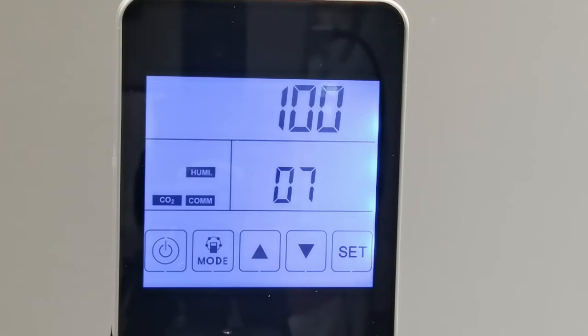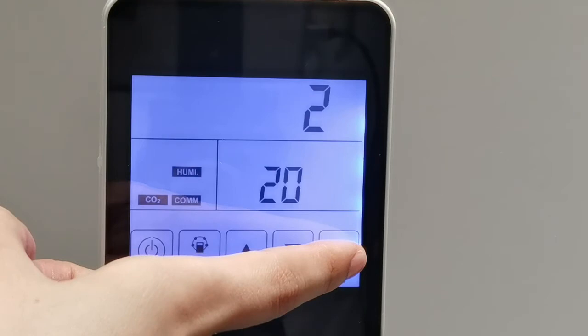Now let's press the set button one more time. Yes, now we move into parameter 08. 08 refers to the central control function to identify the address of ERV. Okay, let's press the set button one more time. Now it's 19 and one more time 20. Okay, 19 and 20 are empty.